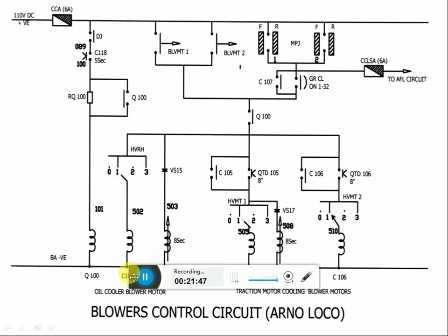For example, in blowers control circuit and BLVMT1 on after closing of DJ, initially C107 will close and HVRH will come into the circuit. At the same time, the relay QTD 105 will energize. After 8 seconds, this interlock will close on C105 coil. After 8 seconds, C105 coil will pick up and contact will close with a delay of 8 seconds. Similarly, C106 also closes with a delay of 8 seconds through QTD 106. To avoid the overloading of Arno at a time, a time gap will be given through this QTD 105, 106.